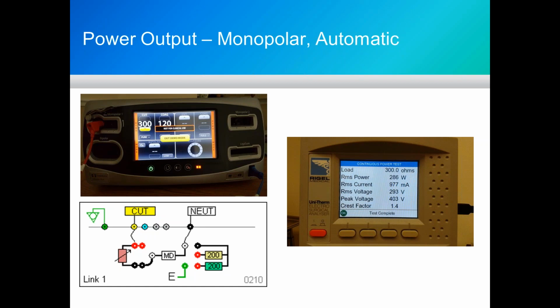We're going to go through a variable power load bank. On the Unitherm, this goes from 5 ohms up to 5,115 ohms in 5 ohm increments, and that power load bank is rated for a full 500 watts for a full continuous minute. Then we're going to go through a jumper to something called MD for measuring device. Actually, that's our internal current transformer, and then back to the patient return.